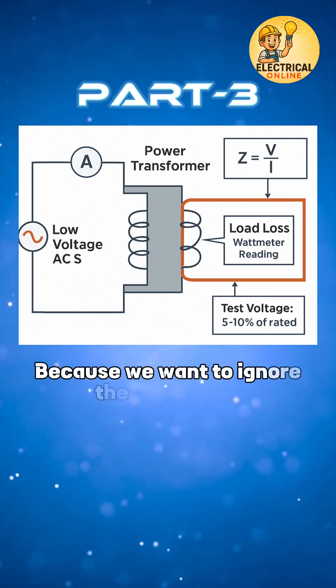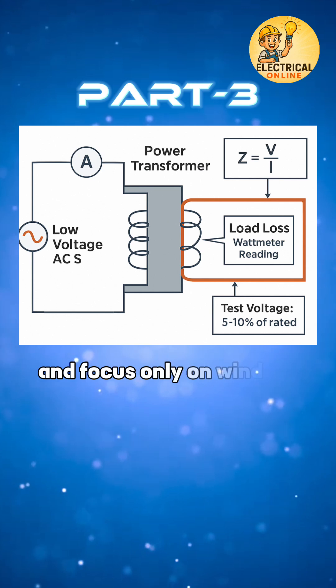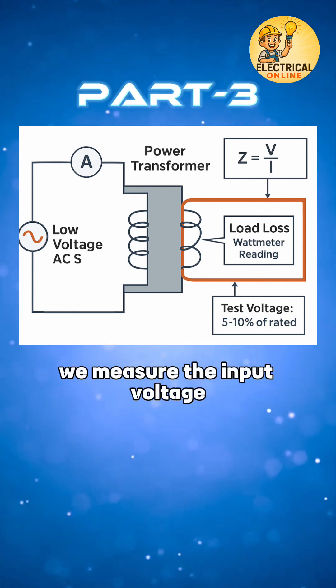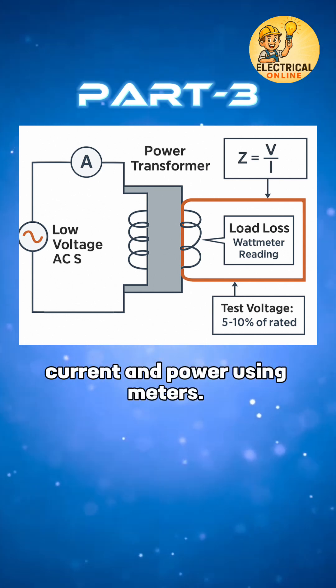Why low voltage? Because we want to ignore the core losses and focus only on winding behavior. We measure the input voltage, current, and power using meters.